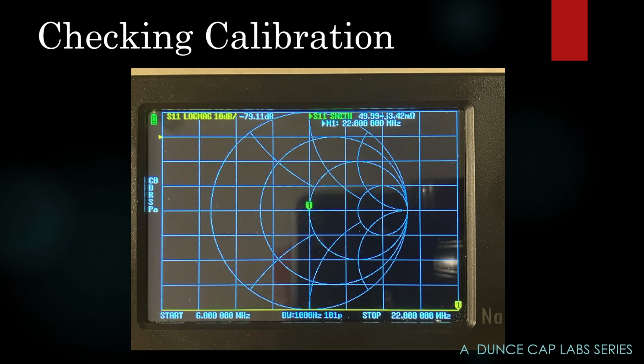Put the dummy load on. The Smith chart should sit right at 50 ohms, right in the middle of the screen, and your return loss should be at max, essentially 80 dB. If you've got those conditions, you're calibrated just fine.